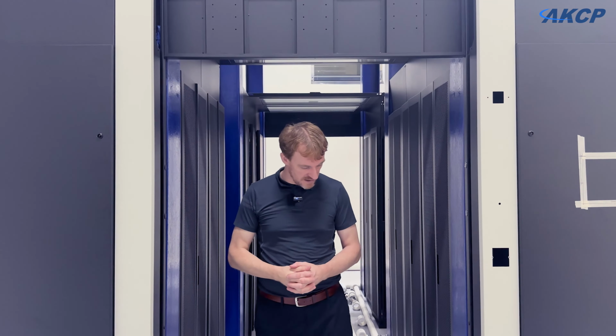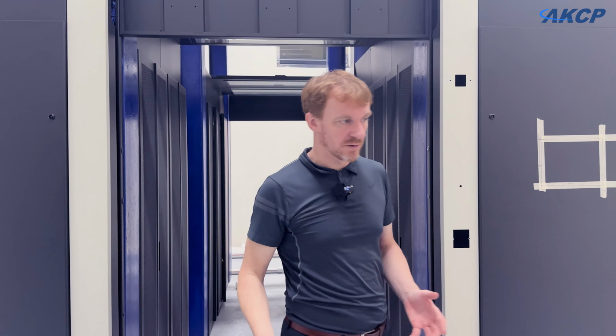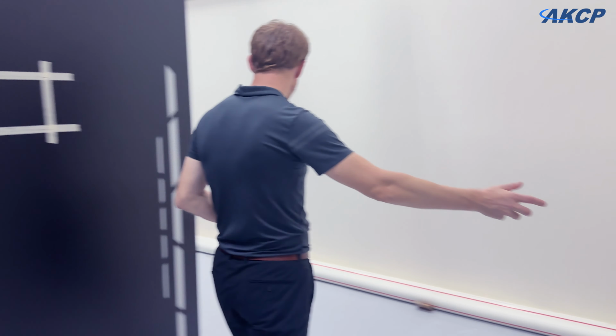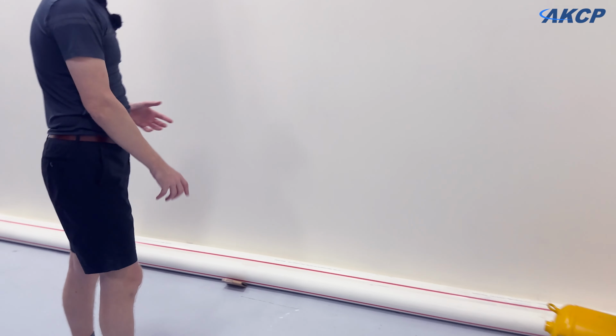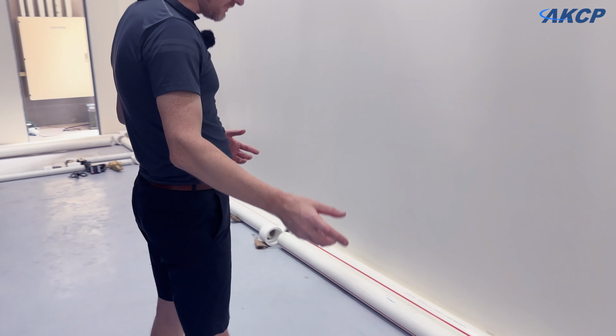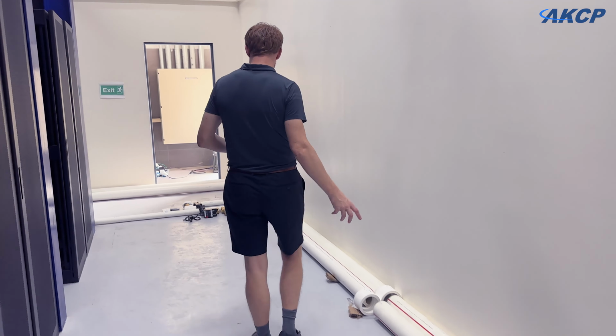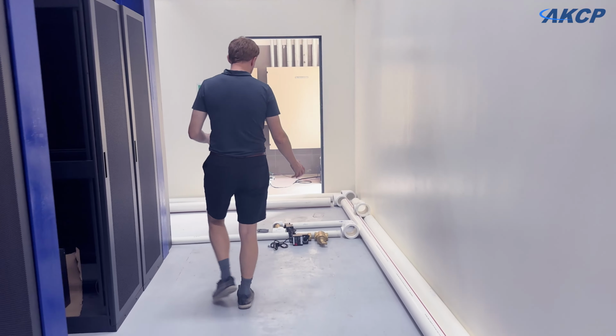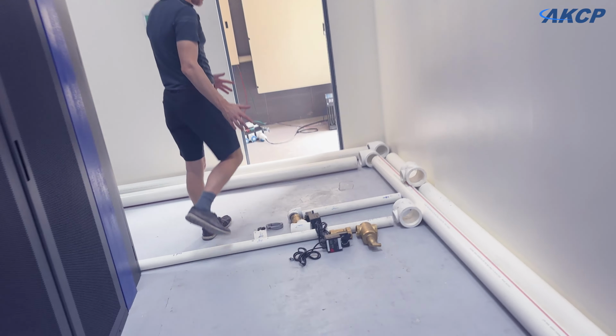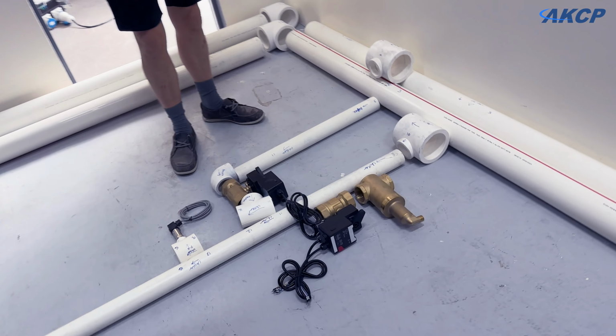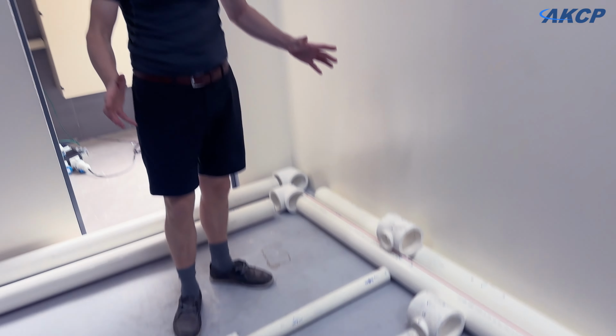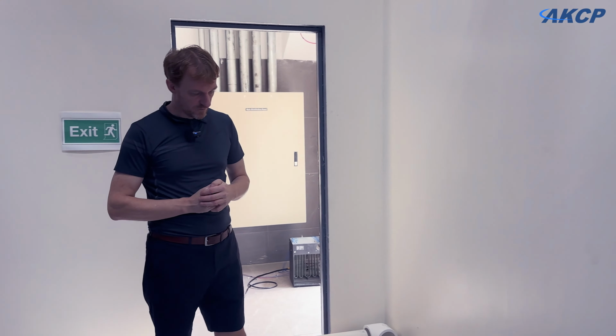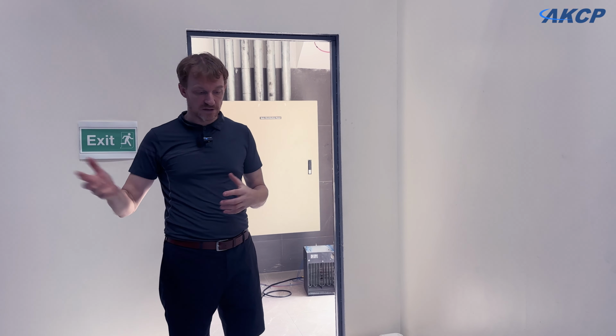The other thing we're working on now is installing the water pipe network. You can see we've been laying it out here on the floor initially, making sure we have all the connections correct. Here's an example of one of our switching stations where we're able to mix water and choose the source of the water coming into the cooling system.